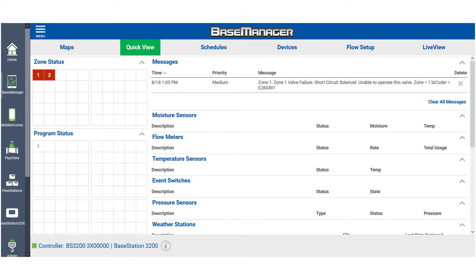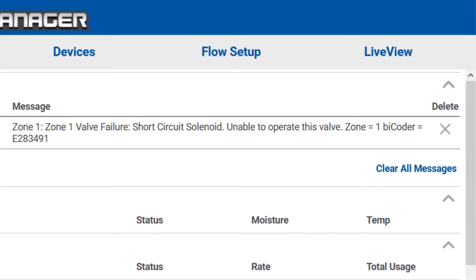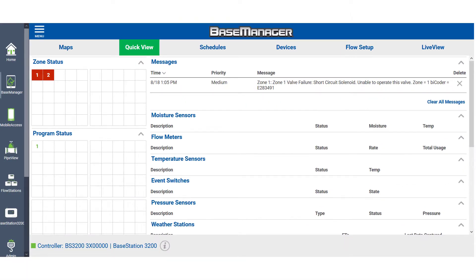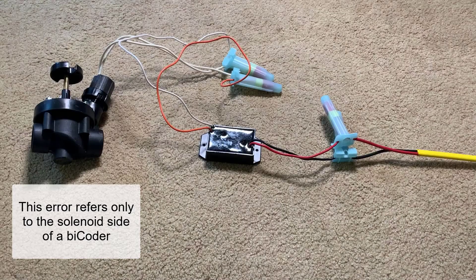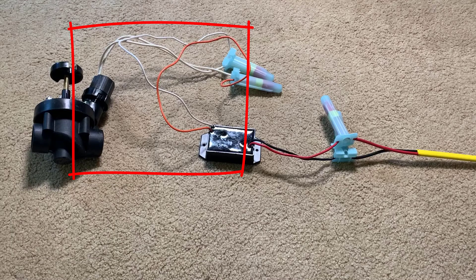Short circuit messages on two-wire systems happen when an assigned zone runs and the controller finds a solenoid with very low or no resistance. When it attempts to run that zone, the controller will log a short circuit message. This error refers only to the solenoid side of the bicoder, not the two-wire side.